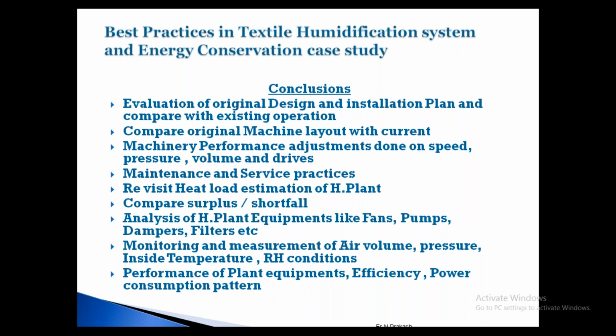Then analysis of equipment like fans, pumps, dampers and so on. We have to see the number of dampers as well as the face velocity and face area of the dampers. They may have given 4 dampers or 5 dampers. What is the size of the damper? That is important because that much airflow has to go through the dampers. We also have to see how the blades are placed, whether opposed blades or parallel blades. Filters: what type of filter they used is also very important, because each filter will add resistance, so each type of filter used has to be checked.